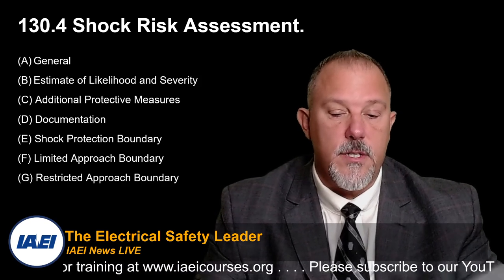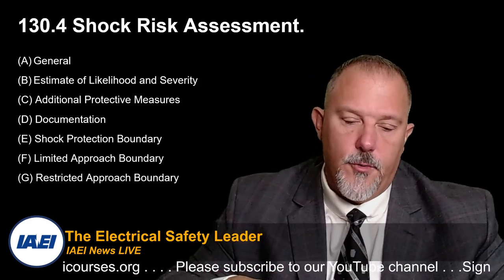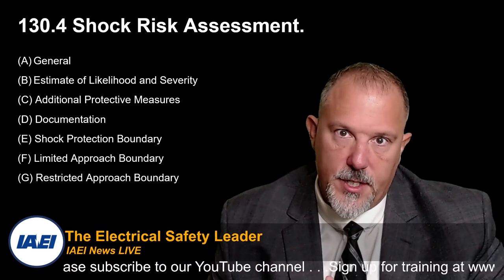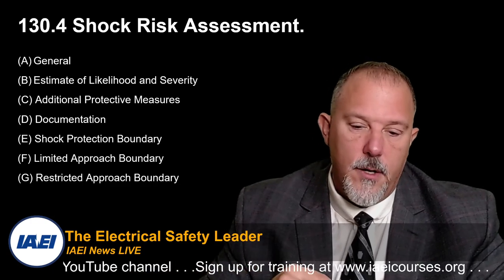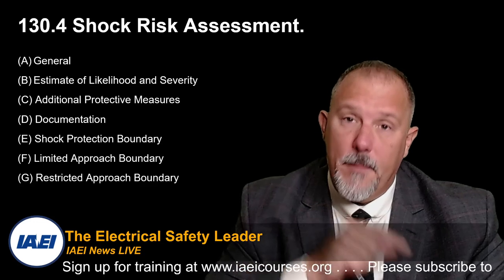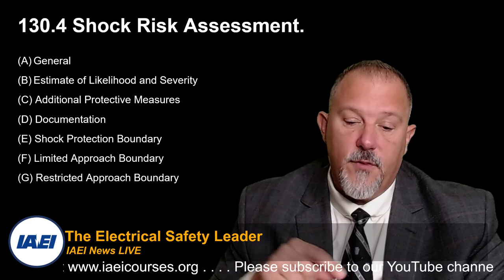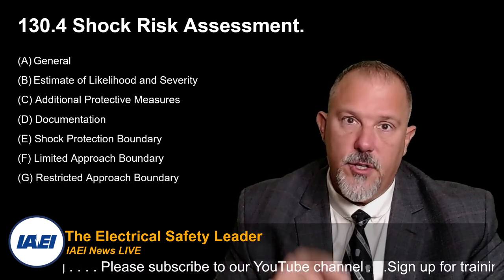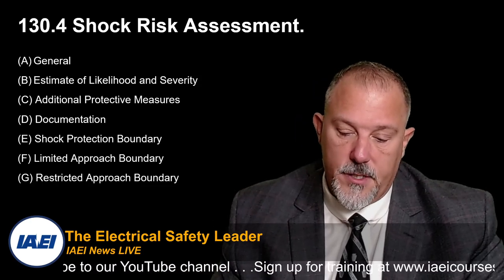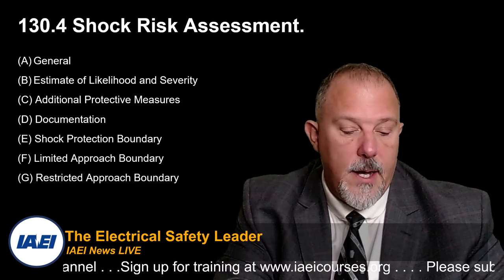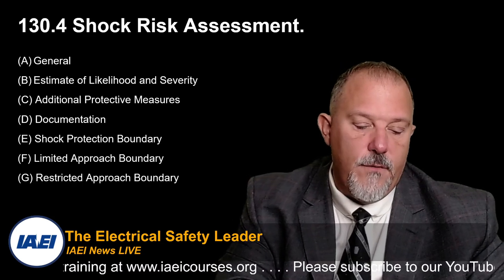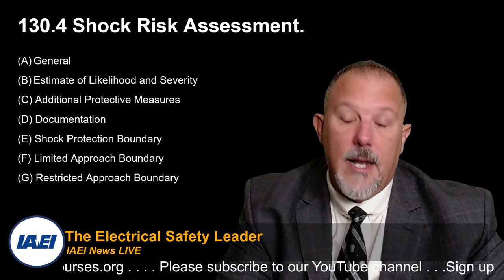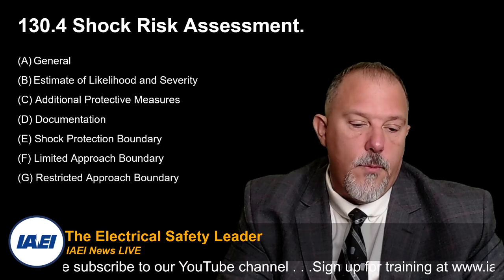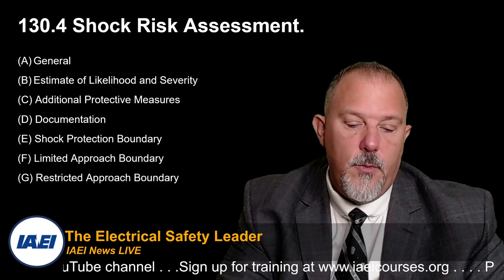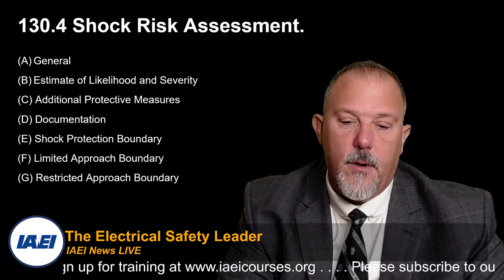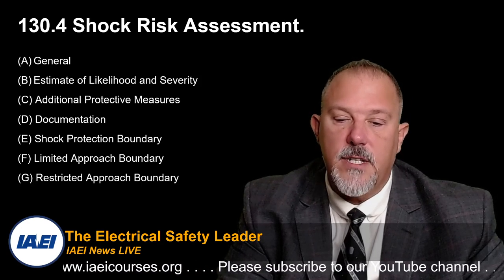What you get into here is that you have to understand who the qualified person is and who the unqualified person is, right? And depending upon who you're dealing with, when they enter either the shock boundary, or they may not be able to enter the limited approach boundary, where you have a restricted approach boundary. So you have shock protection boundaries, which are limited approach boundaries and restricted approach boundaries. So for example, in table 130.4E, say you're at 480 volts. So you're at 150 volts to 750 volts phase to phase. Your limited approach boundary is 3 foot 6 inches. Now, from a limited approach boundary, you're not allowed to have an unqualified person approach nearer than the limited approach boundary of energized conductors and circuit parts.